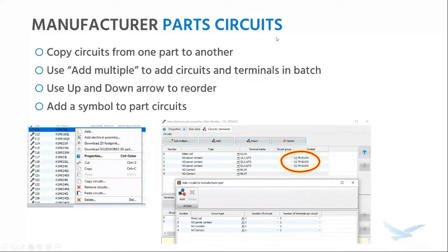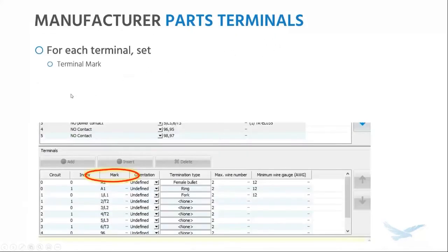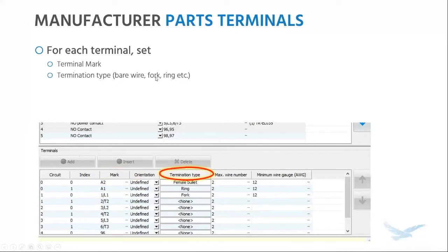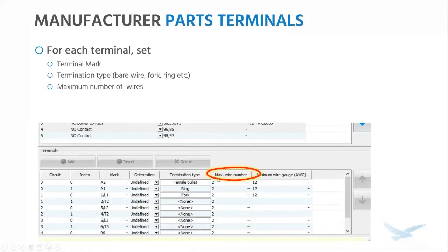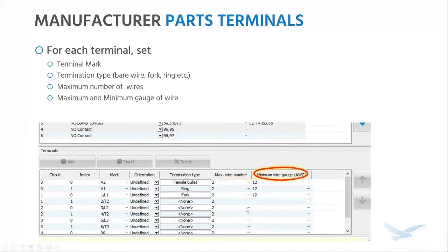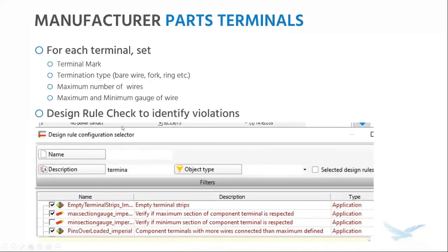These circuits would ideally have terminals as well. For each terminal, you can set up the name of the terminal, which is what's going to give you that accurate wire from-to list. You can also set up the termination type of the wires into that terminal — whether it's a bare wire, fork terminal, ring terminal, etc. That's a feature added in 2019; it's a data field you can call out in a report or a connection label. You can also set up other rules for each terminal: the maximum number of wires that can go in there and limitations on wire sizes. Setting these up lets you take advantage of default design rule checks that will identify violations.